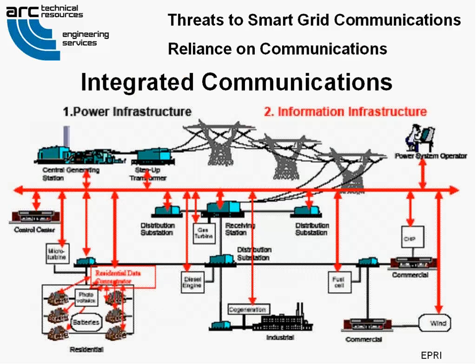Due to its dependency on data acquisition, protection, and control, the modern grid cannot exist without an effective integrated communications infrastructure. Establishing these communications must be of the highest priority, since it is the first step in building the modern grid. This EPRI figure gives one view of the complexity of the integrated communications system required to support the modern grid. The information infrastructure is shown in red. So we're not going anywhere with smart grid without an integrated communication system.